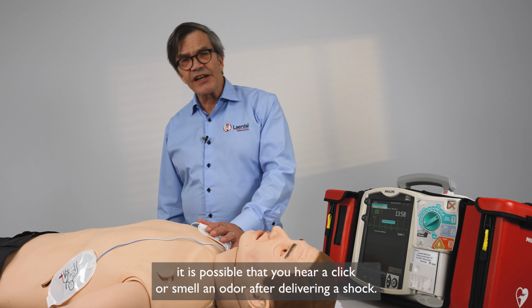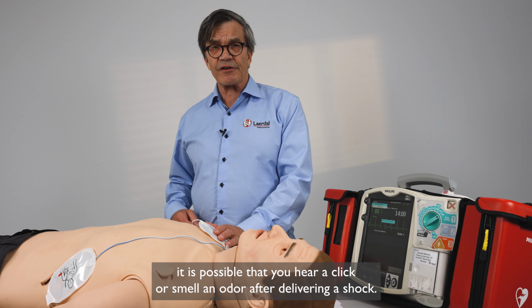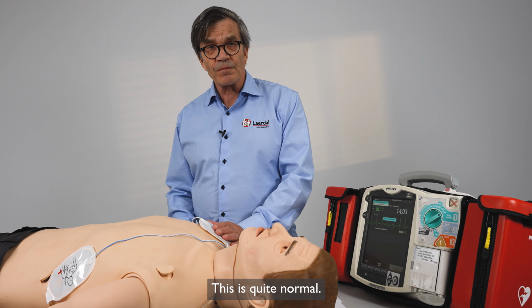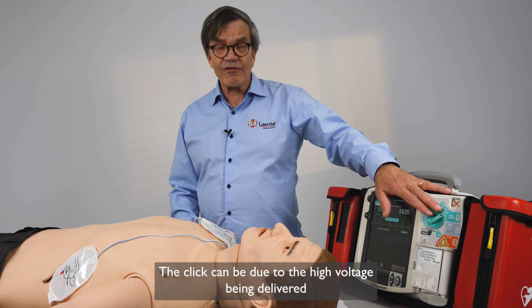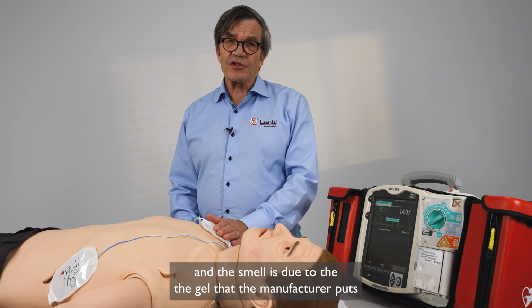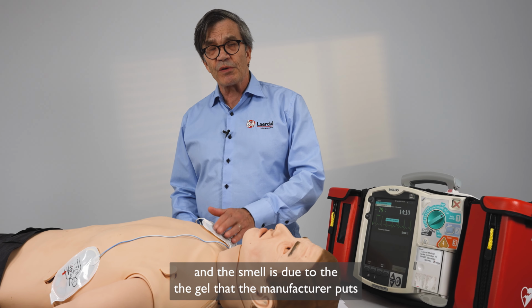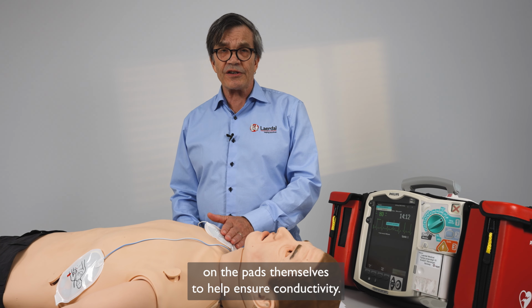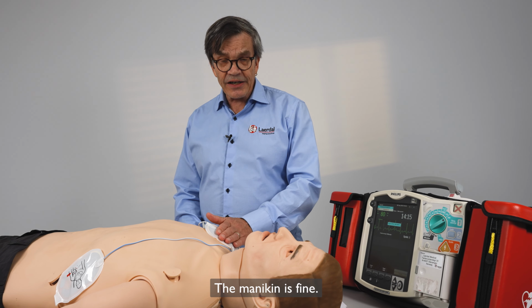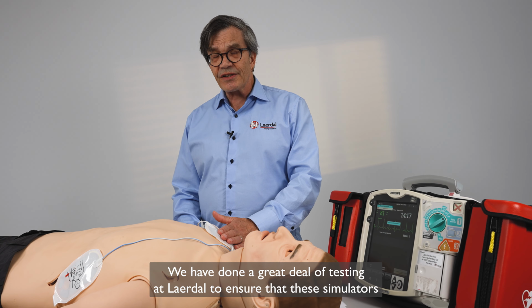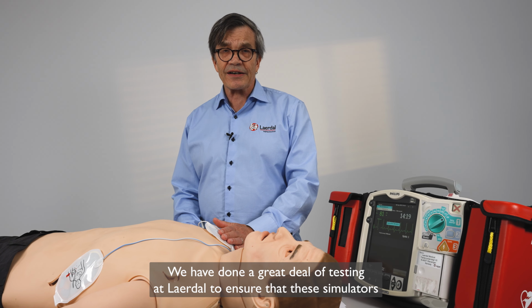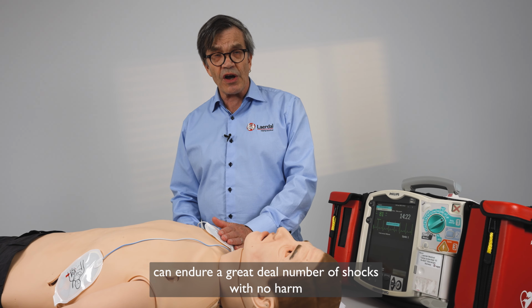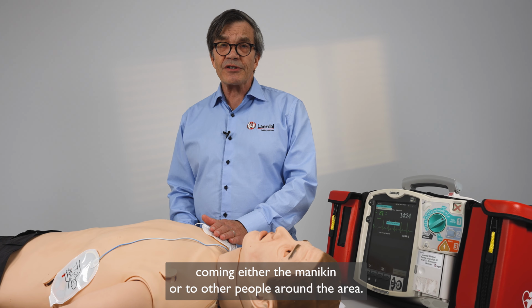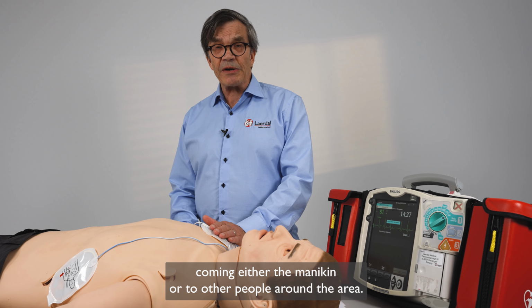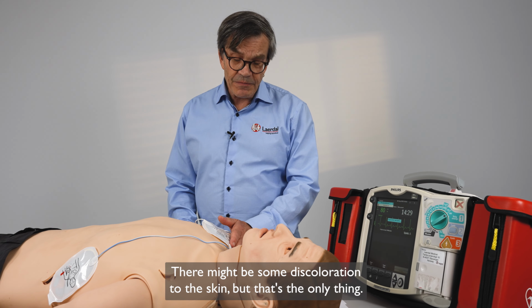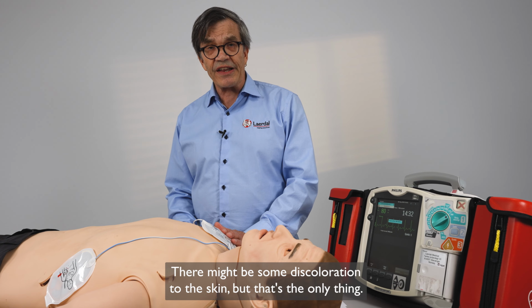It is possible that you hear a click or smell an odor after delivering a shock. This is quite normal. The click can be due to the high voltage being delivered, and the smell is due to the gel that the manufacturer puts on the pads themselves to help ensure connectivity. The mannequin is fine. We have done a great deal of testing at Laerdal to ensure that these simulators can endure a great number of shocks with no harm coming to either the mannequin or to other people around the area. There might be some discoloration to the skin, but that's the only thing.